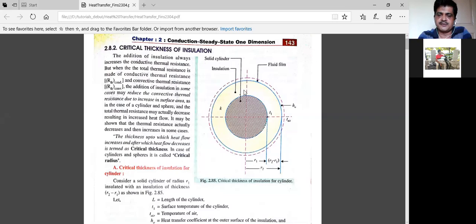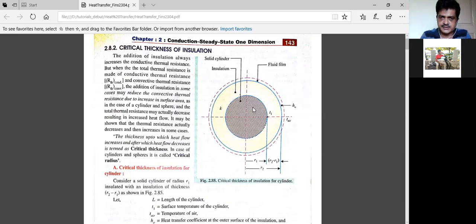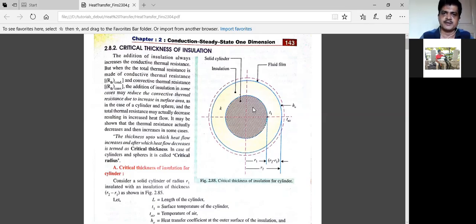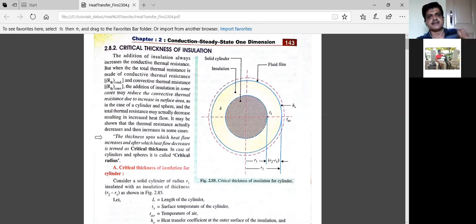Why? Because when you give this insulation material — shown in yellow — when that pipe is surrounded with insulation material, its cross-sectional area increases. If we increase its radius, the cross-sectional area increases, and that insulation material will have more surface area to release heat to the atmosphere. Therefore, though we provide insulation, up to a certain thickness the heat flow will increase; after a certain thickness the heat flow will decrease.